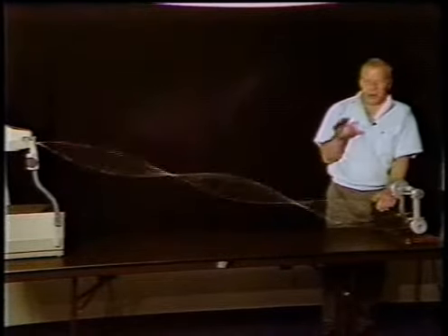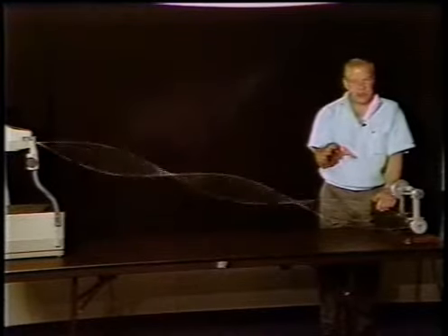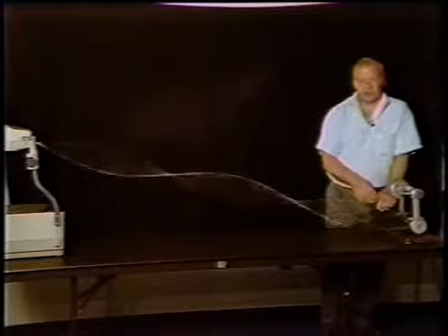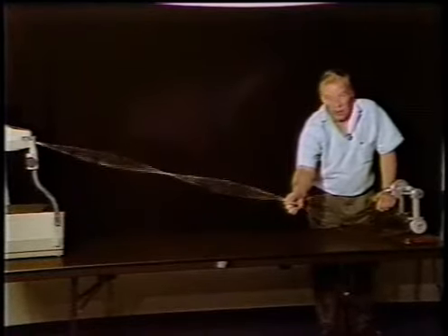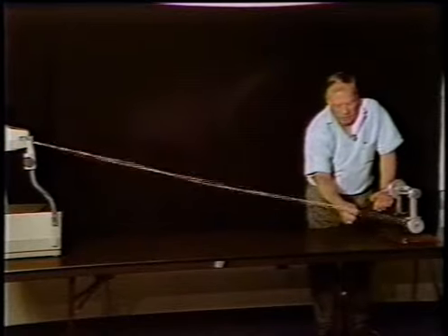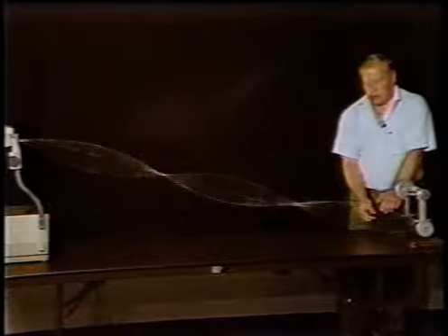What we're indicating here is if you do anticipate making structural modifications or changing the stiffness of the system, it's very, very important to take vibration measurements along the system to find out where these nodal points are so that you can avoid making modifications at those locations. This is the third bending mode of resonance. Let's continue to bring this on up in speed.